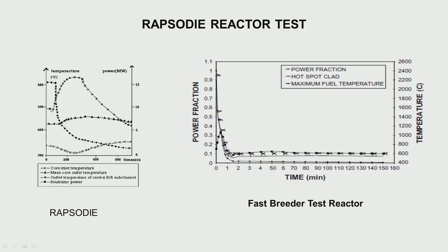Comparing with the Rapsodie reactor test: you can see how the temperature went up, how power came down, and how the mean core outlet temperature changed — more or less similar trends are reflected in our analysis, though on a different scale. The Rapsodie test ran for 10 minutes whereas we ran the analysis up to about 150 minutes and found things remain stable, giving good feedback on fast reactor safety. Even under loss of offsite power, loss of onsite power, and loss of batteries, the reactor shuts down by itself.